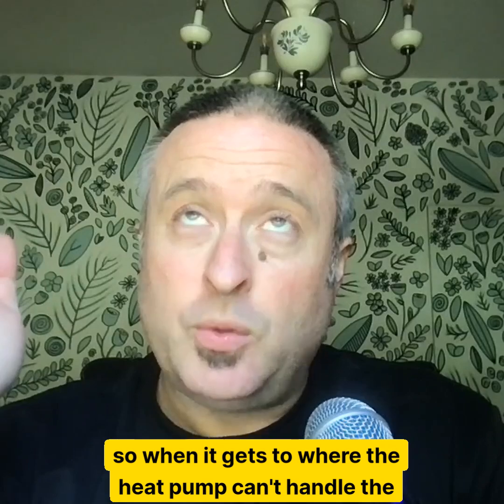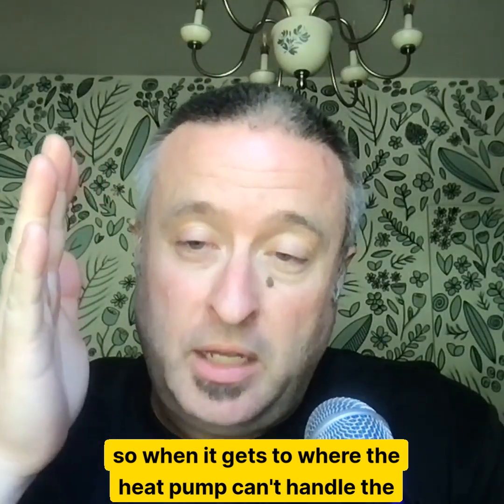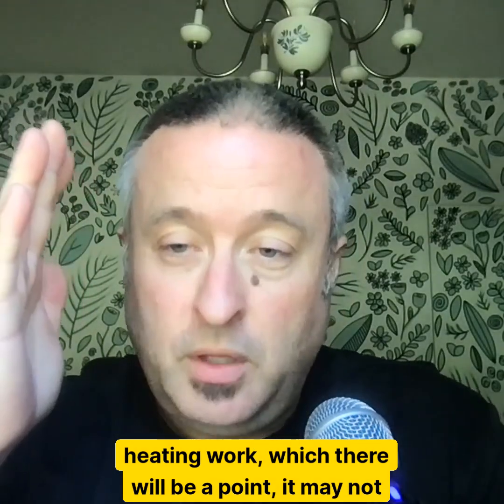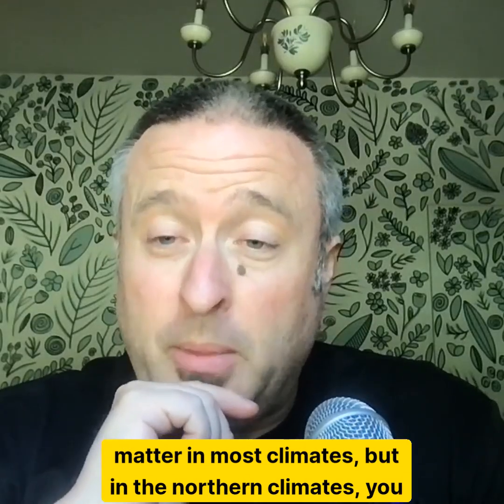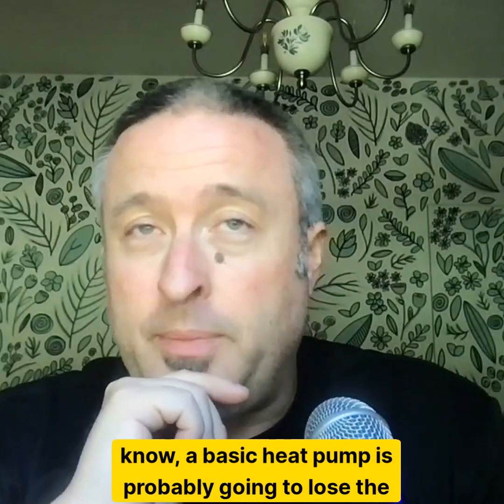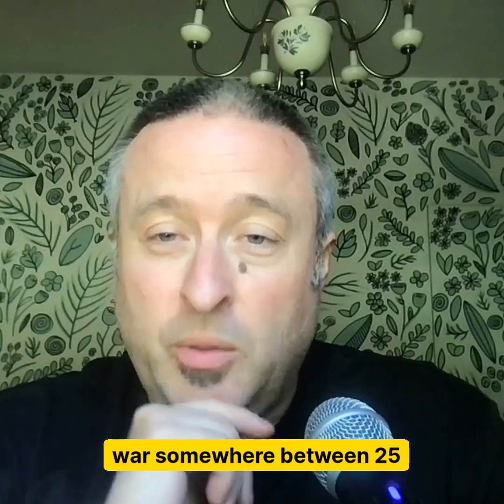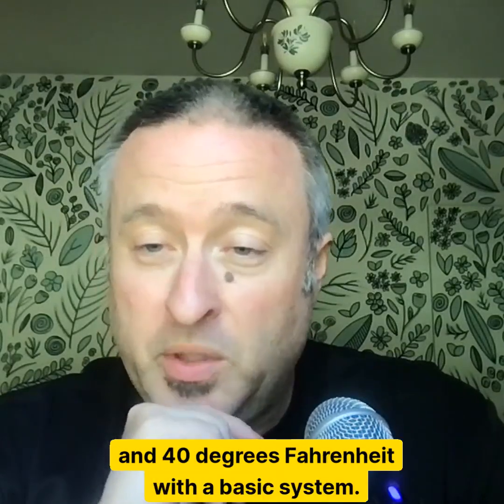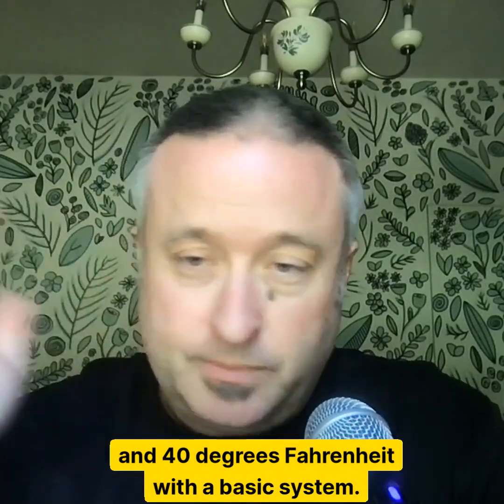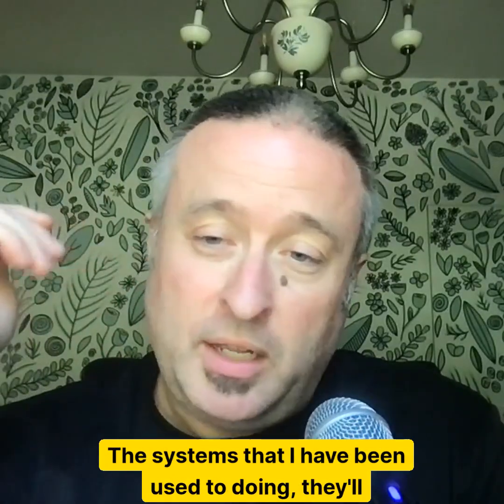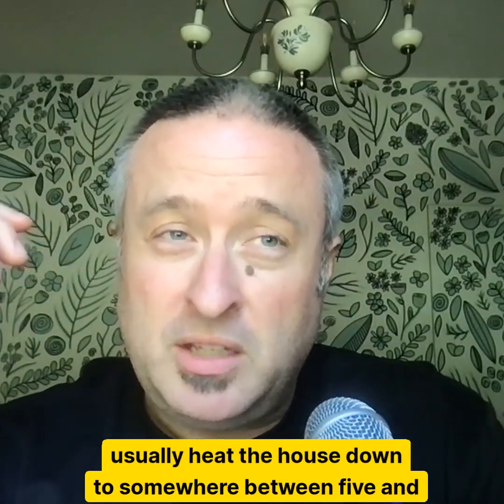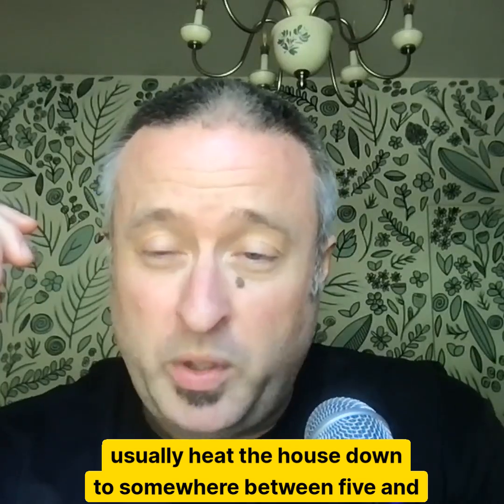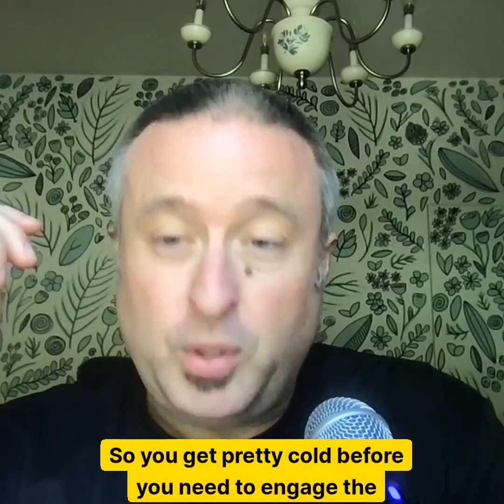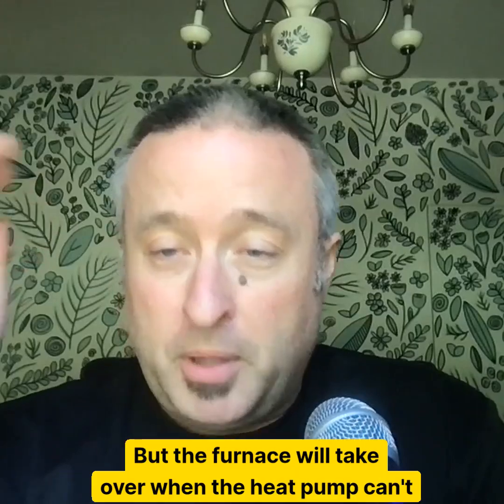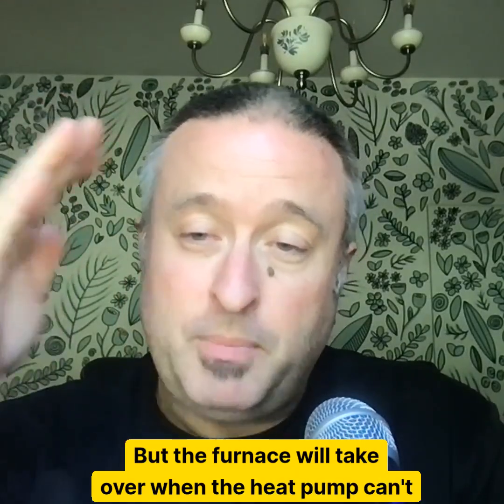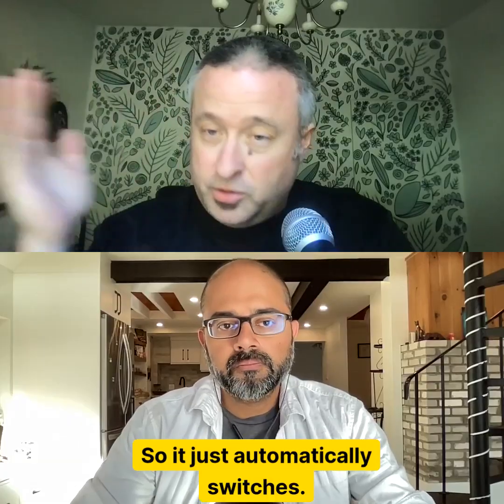So when it gets to where the heat pump can't handle the heating work, which there will be a point, it may not matter in most climates, but in the northern climates, a basic heat pump is probably going to lose the war somewhere between 25 and 40 degrees Fahrenheit. With a basic system. The systems that I have been used to doing, they'll usually heat the house down to somewhere between 5 and 20 degrees Fahrenheit. So you get pretty cold before you need to engage the backup. But the furnace will take over when the heat pump can't do the job anymore. So it just automatically switches.